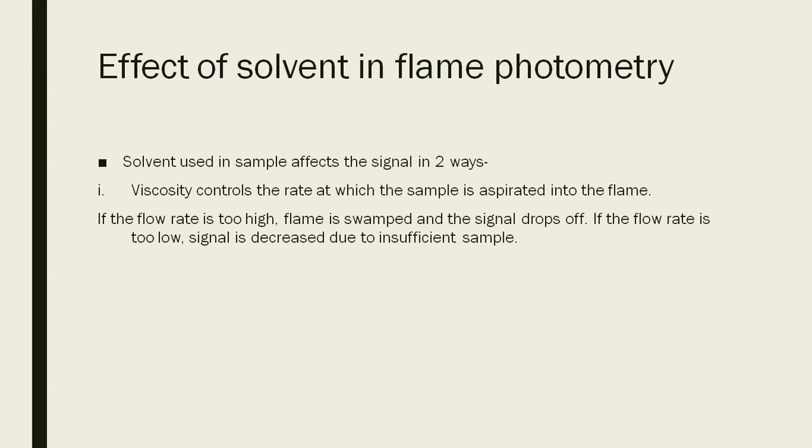First, viscosity controls the rate at which sample is aspirated into the flame. If the flow rate is too high, the flame is swamped and the signal drops off. And if the flow rate is too low, the signal is decreased due to insufficient sample. Therefore, optimum flow rate is important.